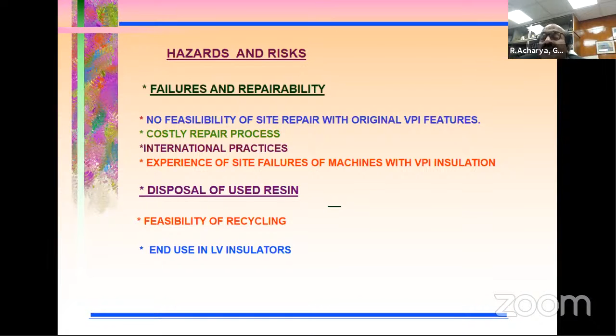At the turn of the last century, generators made for 11 kV applications used a typical thermoplastic insulation system requiring almost 7 to 9 millimeters of radial insulation thickness on the conductor. Today, with the advent of high voltage insulation systems, we use only 1.7 to 1.8 millimeters of insulation for the same 11 kV class. Imagine the progress insulation has made in the last 100 years - from 7 to 9 millimeters down to about 1.8 to 1.9 millimeters. Perhaps with more research into improving insulation conductivity, we can further break the 1 millimeter insulation barrier for a typical 11 kV application. I'm just giving an example.